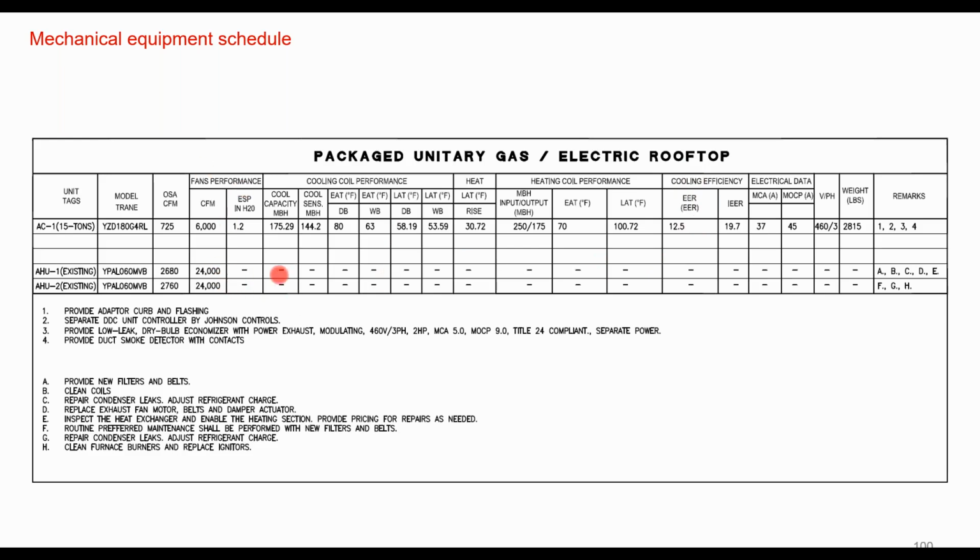You've got a couple of existing units that you really don't have information for. So you might have to fill in some gaps for those based on an older version of ASHRAE or something else. But does anyone see, and I'm putting this out there just to see, is anything missing off of this first unit, AC1, that you would need for the model? There's one very glaring thing that is not included.